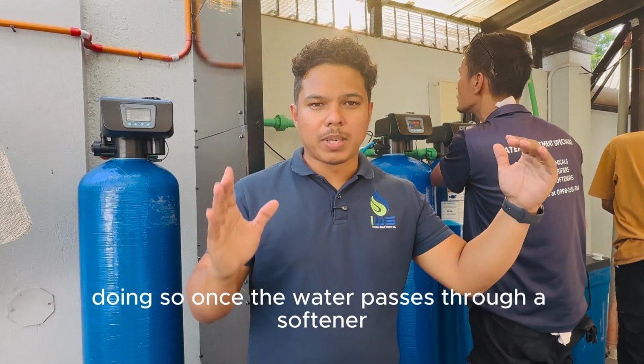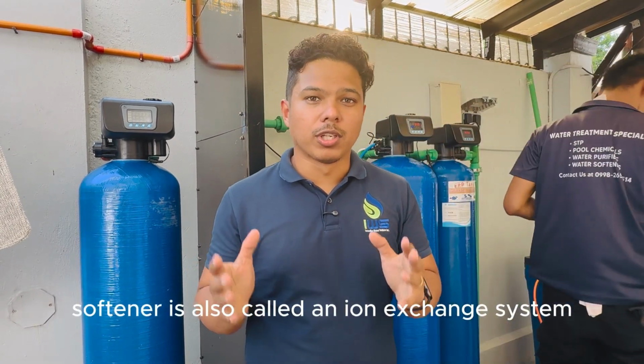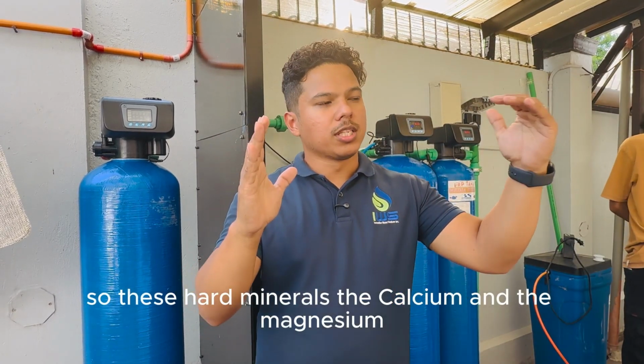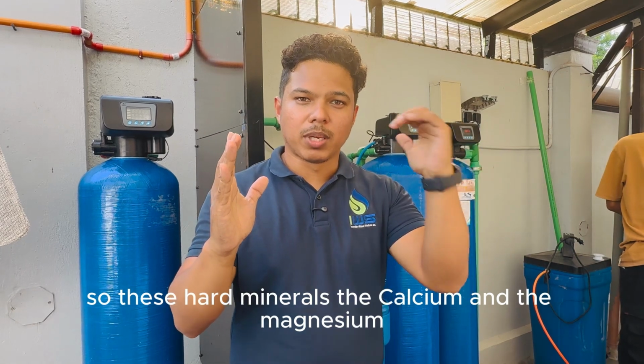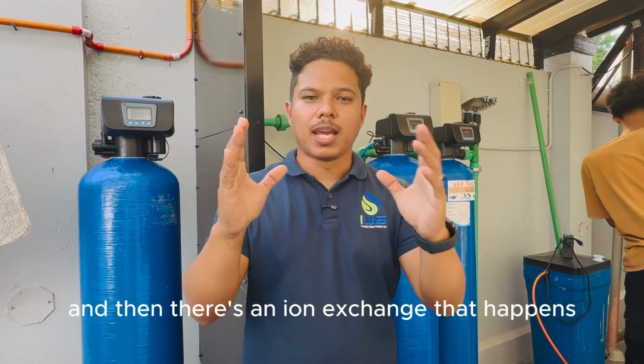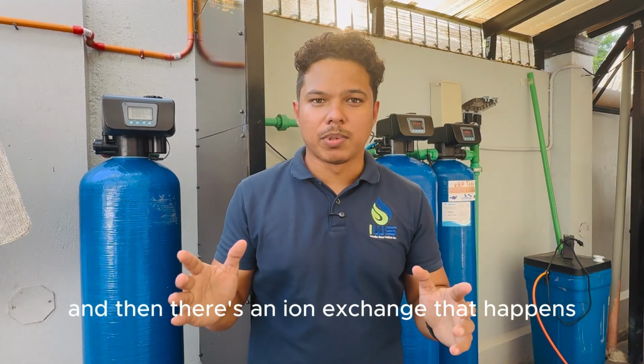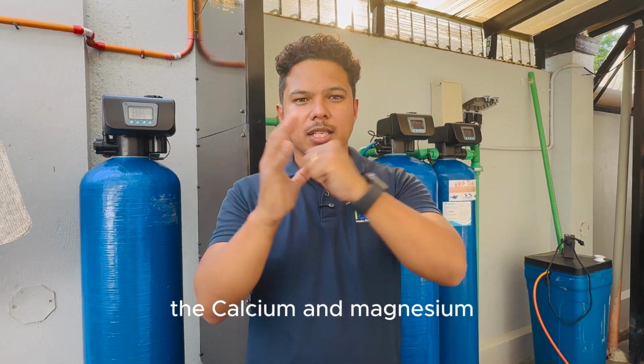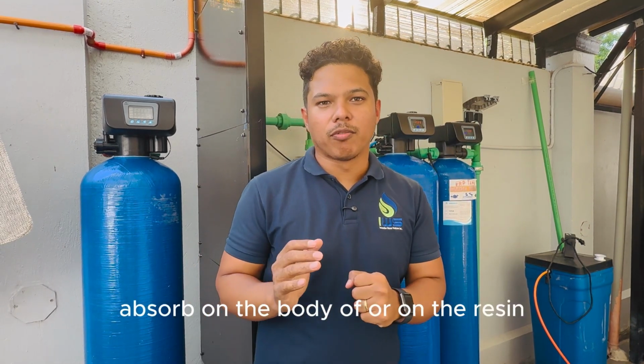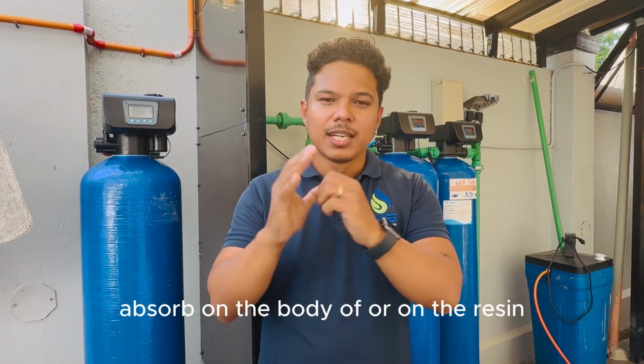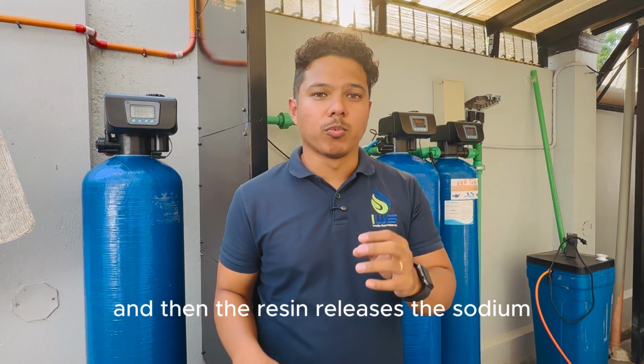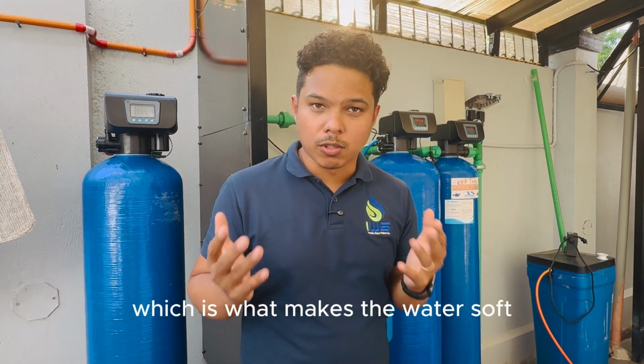Once the water passes through a softener, which is also called an ion exchange system, these hard minerals, the calcium and the magnesium, pass through and an ion exchange happens. Calcium and magnesium absorb onto the resin, and then the resin releases the sodium, which is what makes the water soft.